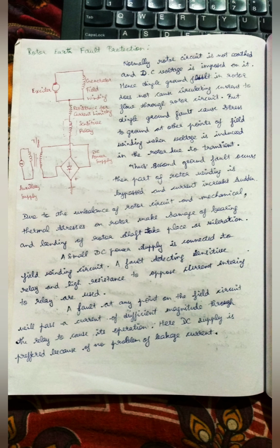Next is the rotor earth fault protection. Normally the rotor circuit is not earthed, and also the DC is imposed on it. Hence a single ground fault in a rotor does not cause circulating current to flow through the rotor circuit.